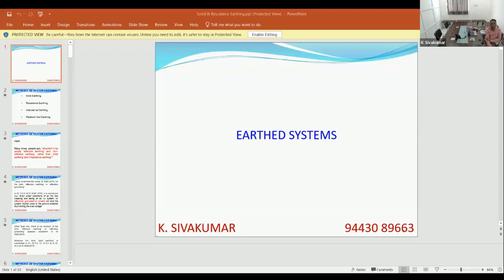Full portion got corroded. After 1 year, they were frequently getting equipment damages because of high voltages during earth faults. So they complained. We went and saw. We could literally pull out the earth electrode with our hand. 1 foot electrode, 3 meter we had put, 1 foot electrode came out. The entire bottom portion was corroded. Yes, actually these areas need improvement.